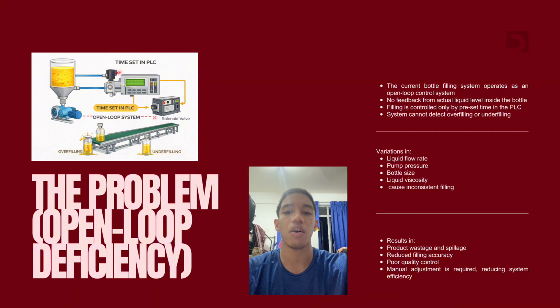If the flow rate or pump pressure changes, or even if the liquid viscosity varies, you will get inconsistent filling. This is going to lead to overfilling, underfilling, and a lot of unnecessary product wastage and spillage. Currently, the only way to fix this is through manual adjustment, which really slows down the efficiency.